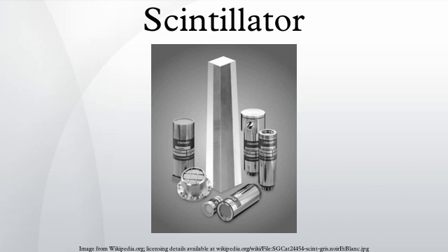CaWO4, or calcium tungstate. CsI(Tl), or cesium iodide doped with thallium. These crystals are one of the brightest scintillators. The maximum wavelength of light emission is rather high, however, making CsI(Tl) best coupled to red-enhanced PMTs or to photodiodes. CsI(Tl) is only slightly hygroscopic and does not usually require an airtight enclosure.